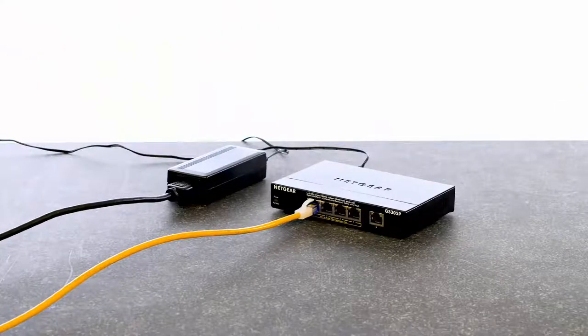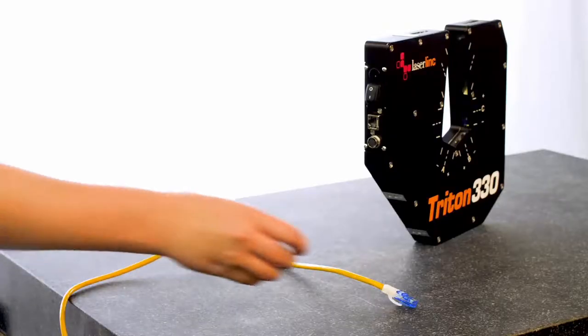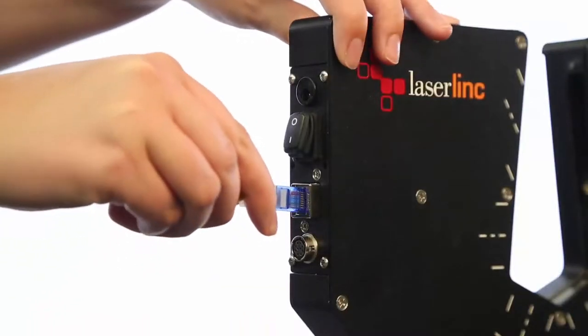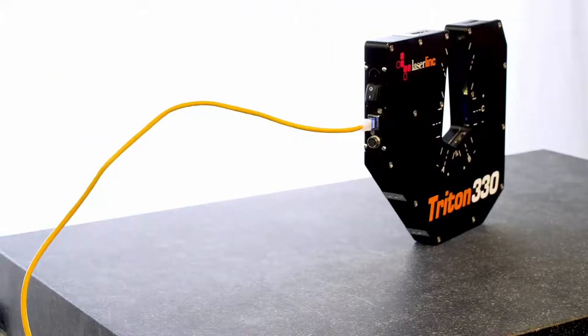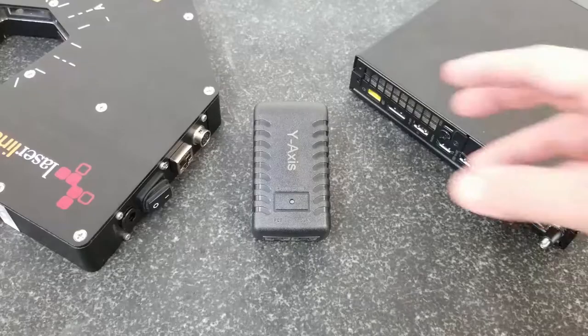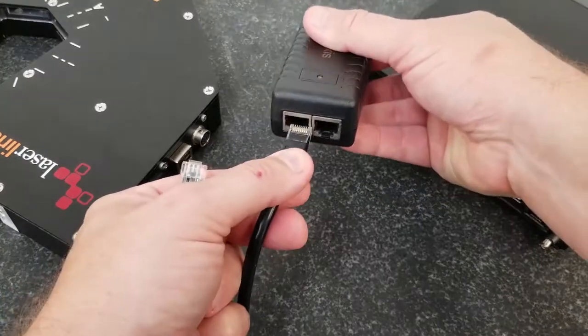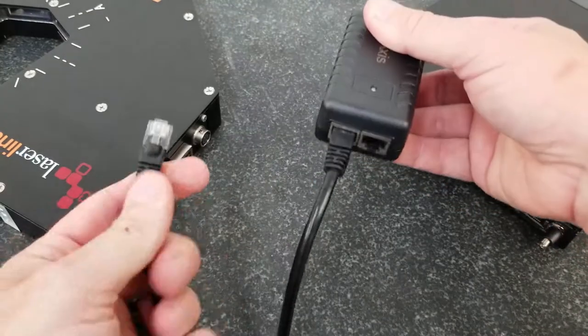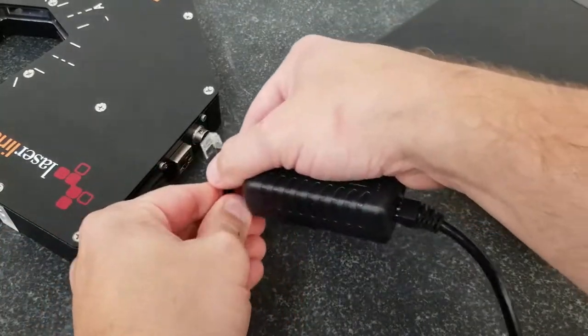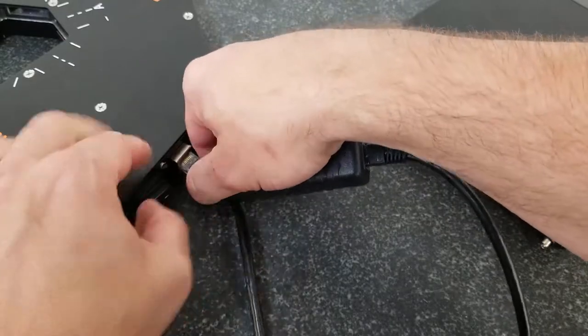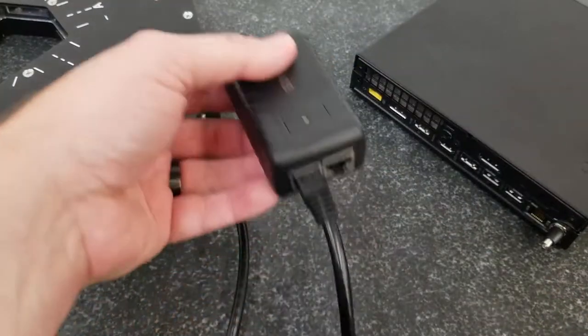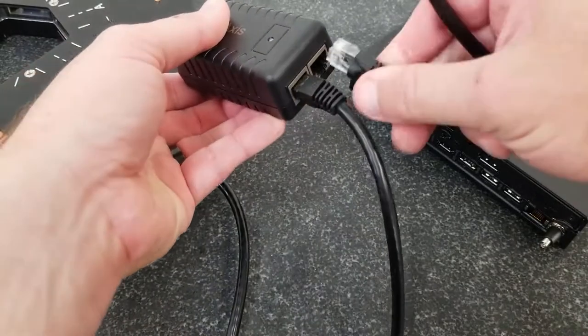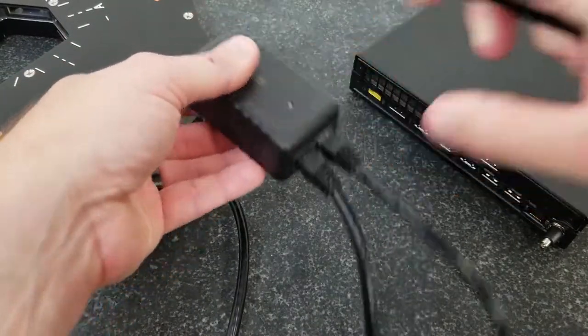The final power type is PoE, or power over Ethernet. If you have a PoE switch, you can power the gauge by connecting it to the PoE switch with an Ethernet cable. If you do not have a PoE switch, you can use a PoE injector to supply power to the gauge over Ethernet. First, connect the switch to the data port on the injector with an Ethernet cable, and connect the gauge to the power port on the injector with another Ethernet cable. Again, we will wait toward the end of this tutorial to plug the switch or injector into power.